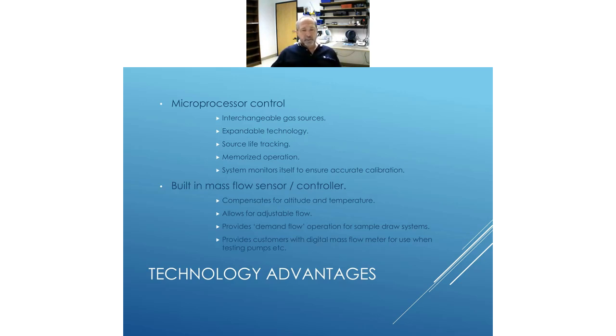The mass flow sensor and controller compensates for altitude, I mentioned that earlier, and temperature, and it allows you to adjust. A lot of sensors have their own built-in pump system where they're drawing a sample from the air from somewhere. So these gas generators that we manufacture allow for adjustable flow. You can shut the pump off. The mass flow sensor will read the flow that the sample-drawing sensor is pulling at, and it will provide whatever gas concentration you tell it you need, however many parts per million the manufacturer asks for.